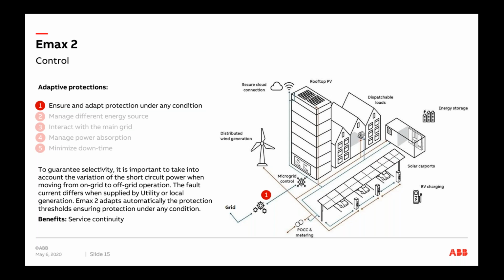That's quite easy with adaptive protection, which in practical terms we call dual settings, allowing us to have two sets of settings within the Emax 2 breaker to accommodate different sources at different times. Now, the dual settings are also helpful when we are looking at arc fault reduction. So, giving you a scenario, if you're looking at a maintenance setup where the protection is set at high fault levels, but there's a physical intervention of service personnel on site, we would like the breaker to trip a lot earlier than at a large current. So you can set them all the way down, quite easily actuated through a switch or some kind of push button setup in a remote location. By pressing a button, it actuates a different set of protections on the breaker, so everything switches down to a level which is a lot more manageable.